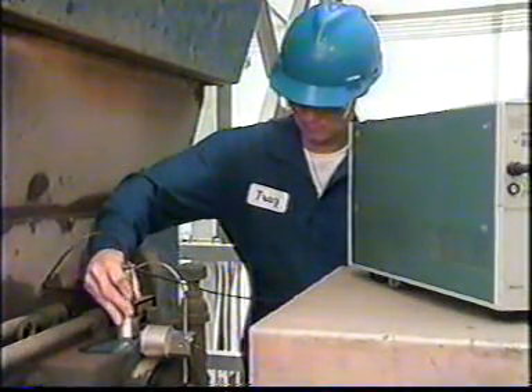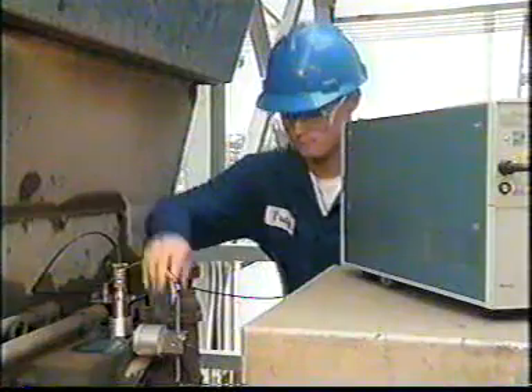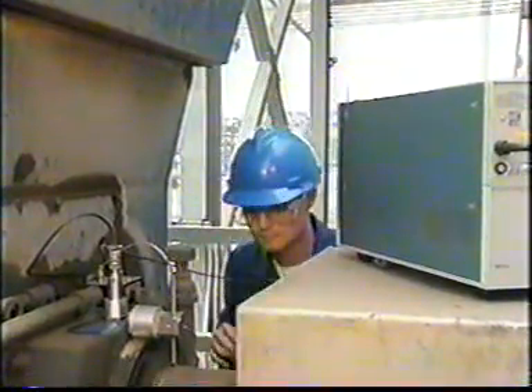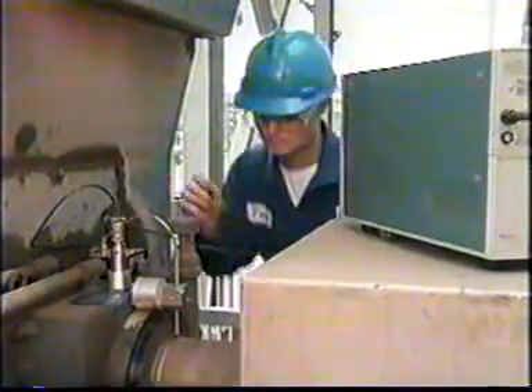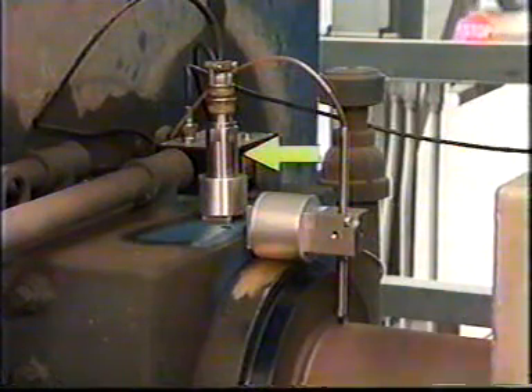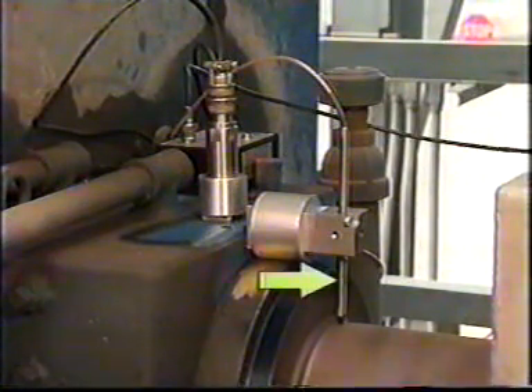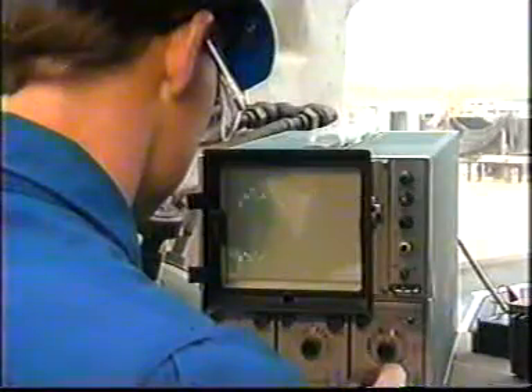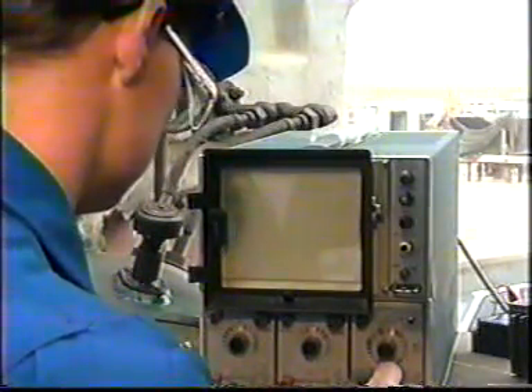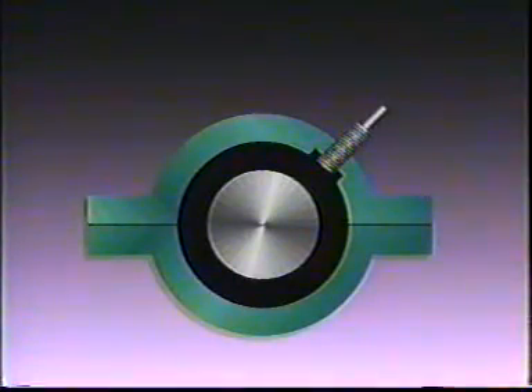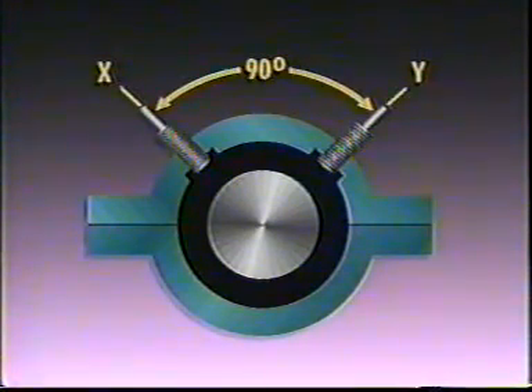Many times, a single probe won't provide enough information. For example, 2 or more probes may be required to find the absolute motion of a shaft relative to a fixed point: a velocity or acceleration probe to measure casing vibration, and a proximity probe to measure shaft position. The difference between the 2 readings provides absolute shaft motion. A single sensor can only give a displacement measurement relative to its position. By positioning 2 sensors 90 degrees apart, we can get a full radial view of motion, measuring shaft vibration in both the X and Y axes.